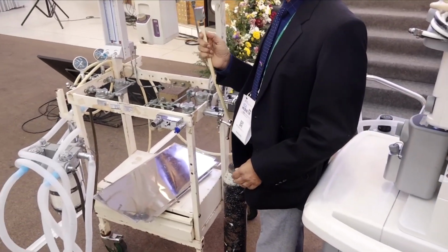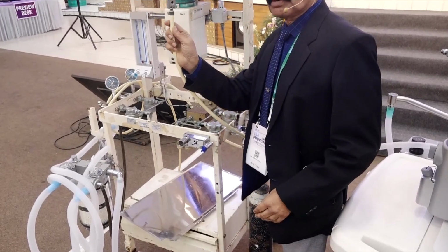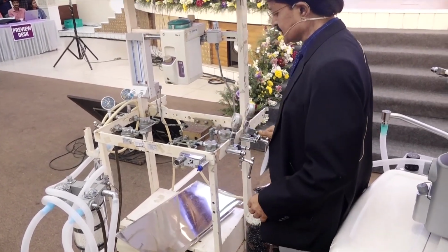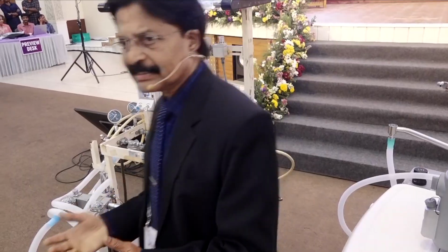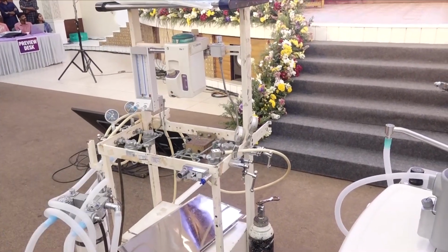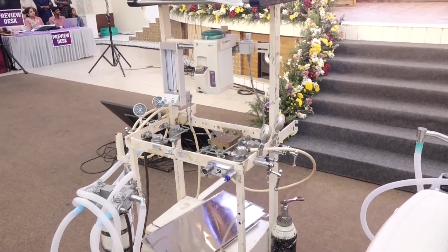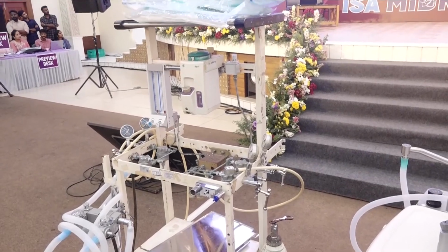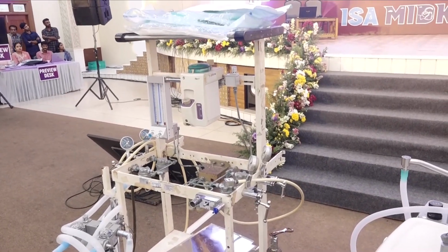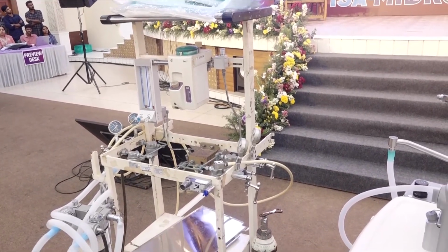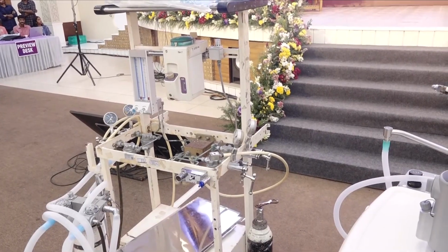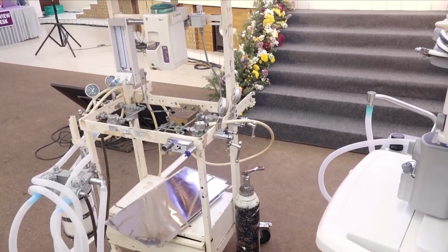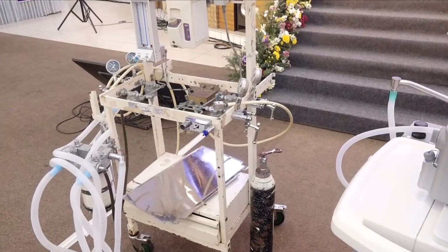In older machines you have to connect the pipelines using this yoke block to the yoke assembly, where you would otherwise connect the cylinder. Now, the pipelines in the workstations are connected at a pressure of 55 to 60 pounds per square inch, whereas the cylinder pressure is reduced to 45 psi.